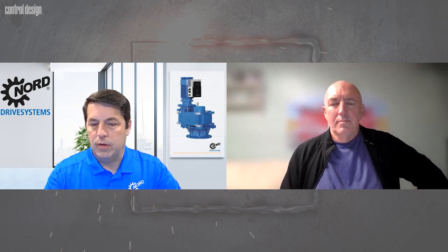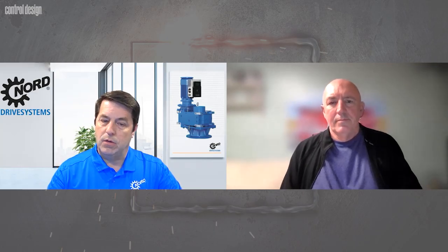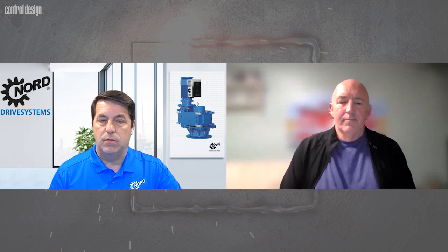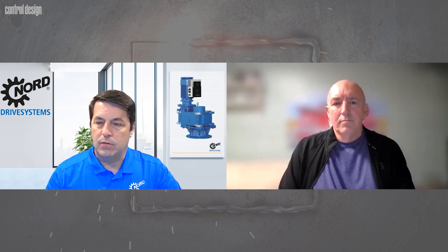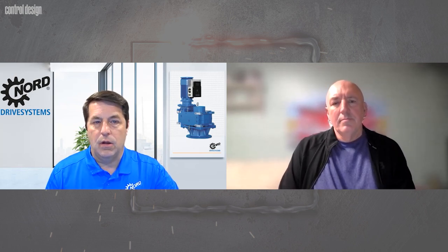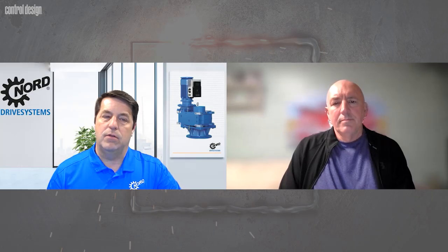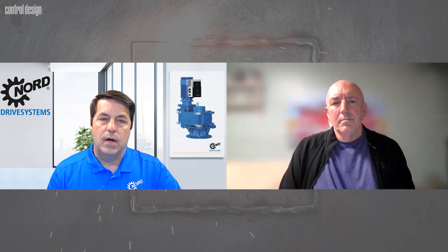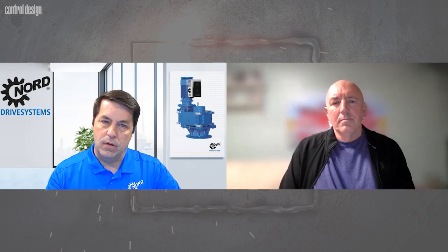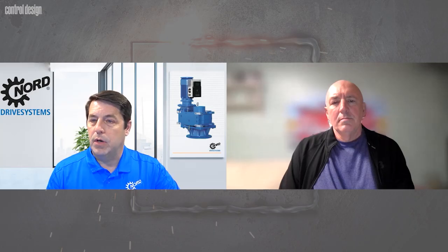So when we move into decentralized, we're taking that VFD out of the electrical panel, putting it out on the machine or on the motor itself, mounted to the motor. And that brings some advantages, particularly in large footprint installations where you're covering a lot of geography. It can lower your installation costs by minimizing the cabling and the wiring between components.